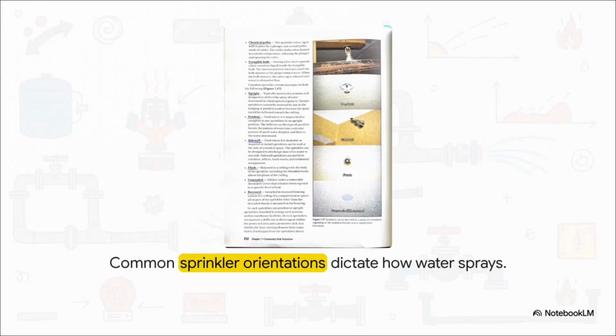And they don't all look or point the same way either. The orientation dictates how the water actually sprays into the room, which is controlled by the deflector attached to the frame. Firefighters are highly trained to spot these visual cues. For an upright sprinkler, which points up toward the ceiling, the deflector creates this nice umbrella shape. For a pendant sprinkler, which hangs down, the deflector has these fanned, larger teeth to push a circular pattern of droplets downward. Then you have sidewall sprinklers that shoot water sideways.